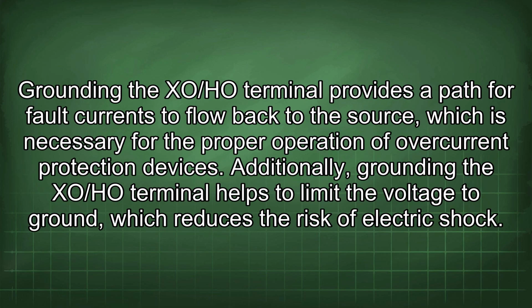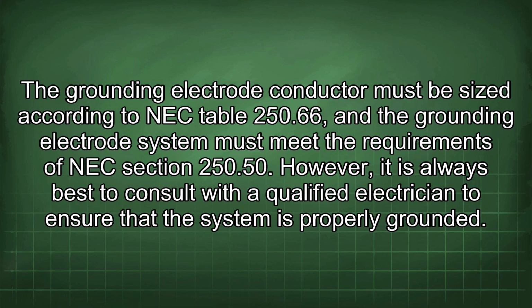Grounding the XO/HO terminal provides a path for fault currents to flow back to the source, which is necessary for the proper operation of overcurrent protection devices. Additionally, grounding the XO/HO terminal helps to limit the voltage to ground, which reduces the risk of electric shock. The grounding electrode conductor must be sized according to NEC Table 250.66, and the grounding electrode system must meet the requirements of NEC Section 250.50. However, it is always best to consult with a qualified electrician to ensure that the system is properly grounded.